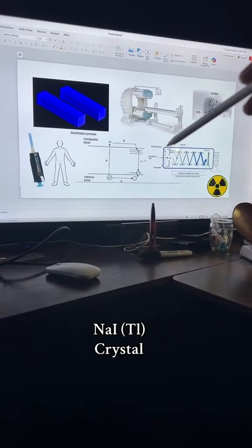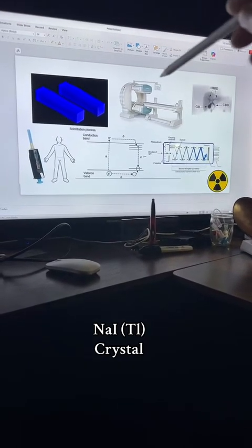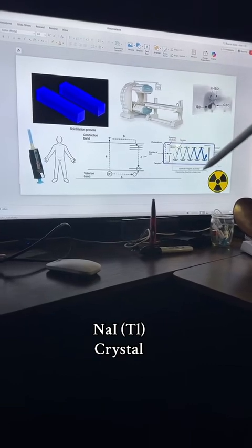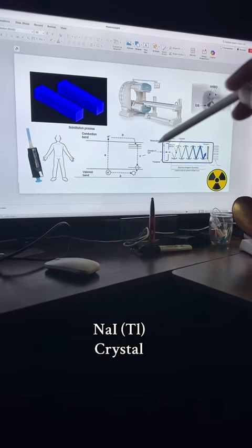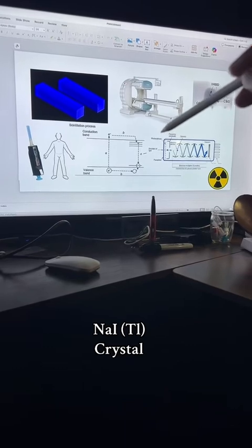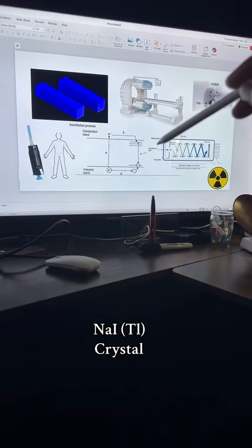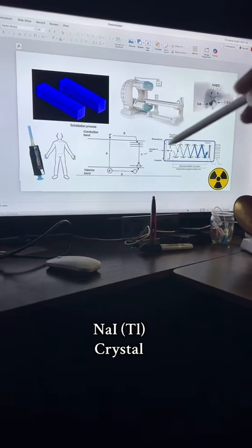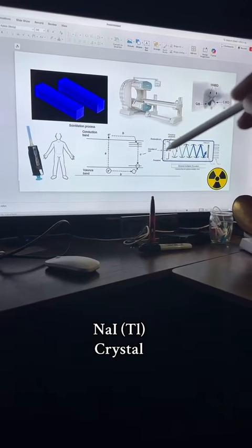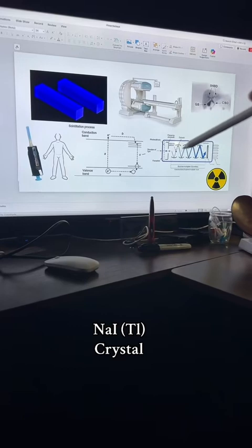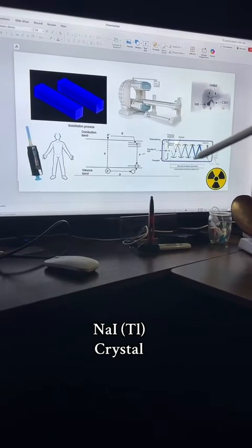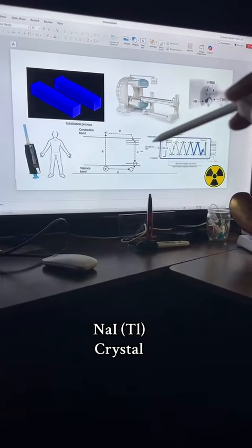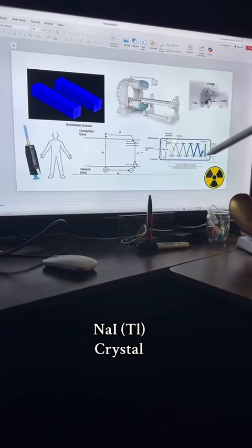So we have on top of these crystals, on camera heads 1 and 2, these PMT tubes that pick up those light signals. That light photon, just for this particular example, strikes the photocathode. Once it strikes the photocathode, an electron is produced, and then more electrons are produced proportional to the photon energy. That way the camera can see the signal.